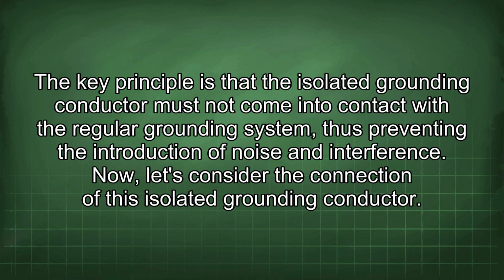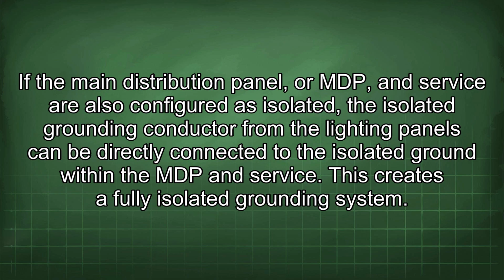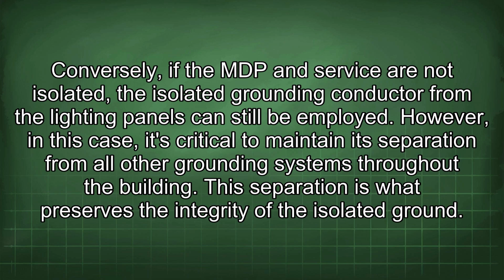Now let's consider the connection of this isolated grounding conductor. If the main distribution panel, or MDP, and service are also configured as isolated, the isolated grounding conductor from the lighting panels can be directly connected to the isolated ground within the MDP and service. This creates a fully isolated grounding system. Conversely, if the MDP and service are not isolated, the isolated grounding conductor from the lighting panels can still be employed. However, in this case, it's critical to maintain its separation from all other grounding systems throughout the building. This separation is what preserves the integrity of the isolated ground.